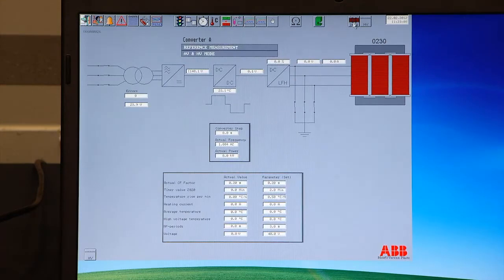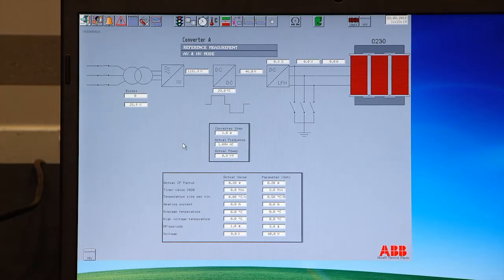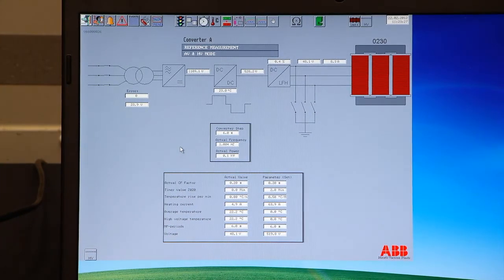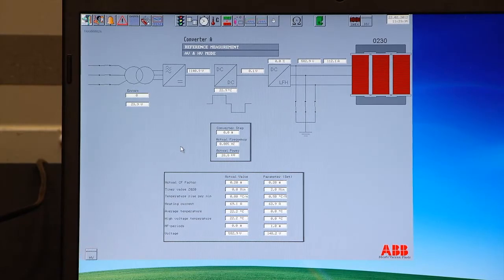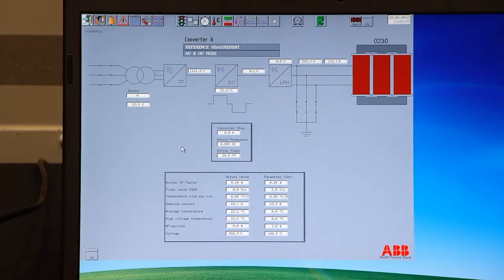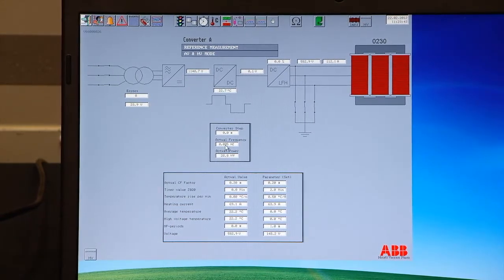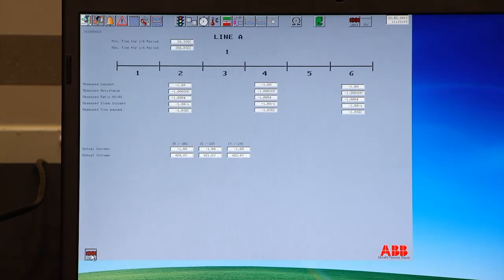Can go and see what's happening with the converter on this page. We see now that we have closed the main switch, the main incoming power. We have now our 1140 volt on the DC link. And the system is running automatically. And now when the main switch is closed, we also have the lights coming on, flashing on the trailer. So what we can see here is that now he has done the average measurement resistance readings. He has already switched to the lower frequency to 5 millihertz and is ready now to go for high voltage resistance reading. You click on the bottom in the left corner, lower left corner, and you will eventually see what's happening on this one.